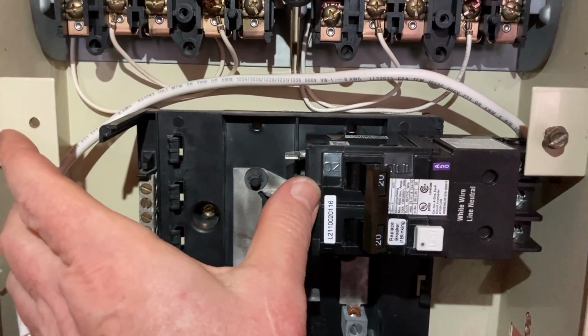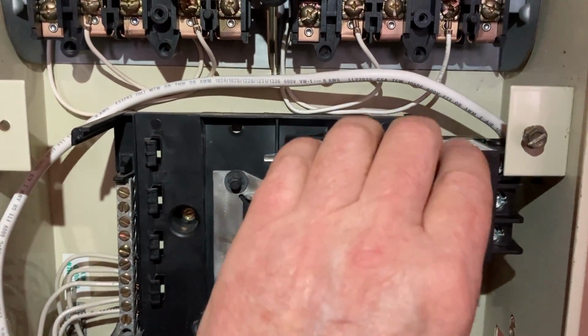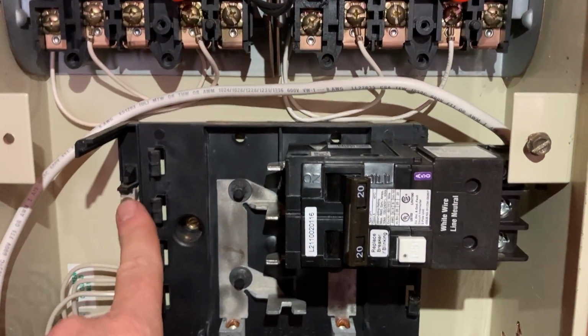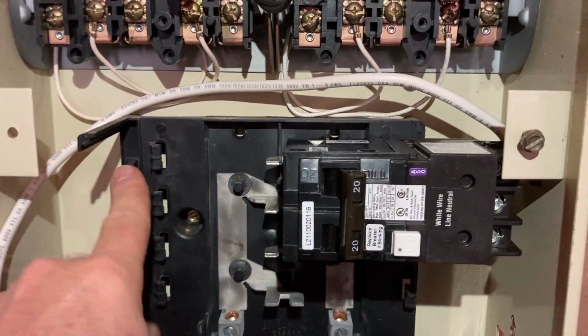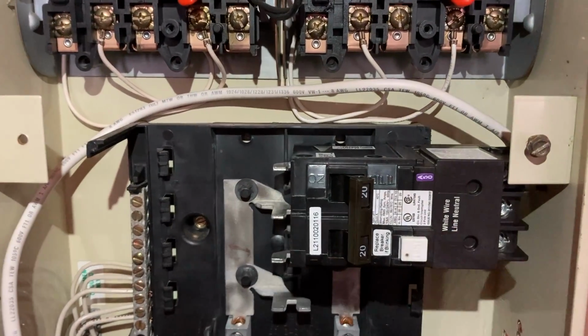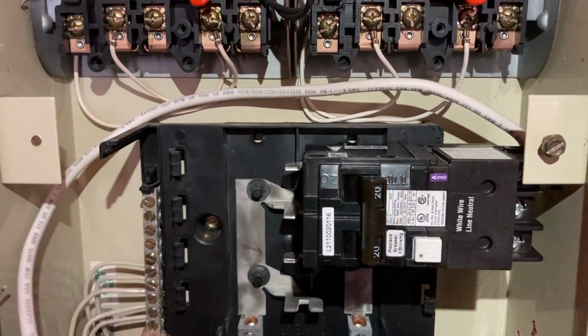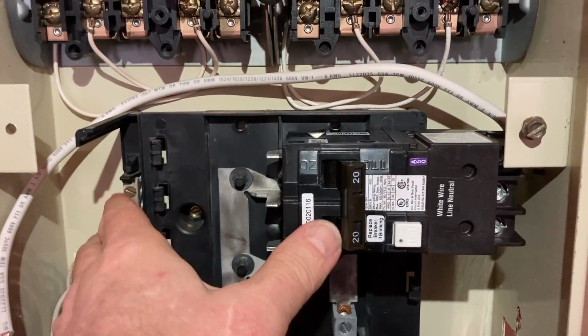I was going to put this breaker here, but I'm going to have to put it over here because this little plastic tab that holds the neutral bar is in the way. It pokes up into the big butt of this huge circuit breaker. So I guess that's another reason why you should only use breakers listed for the panel you're working in, but we'll make it work.